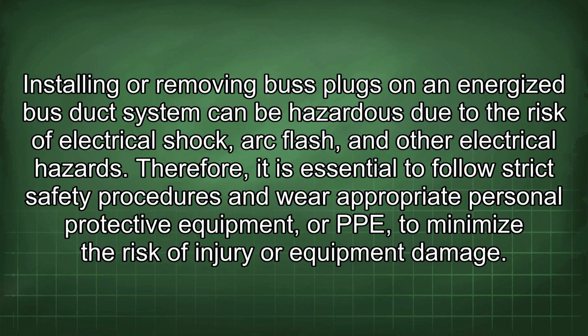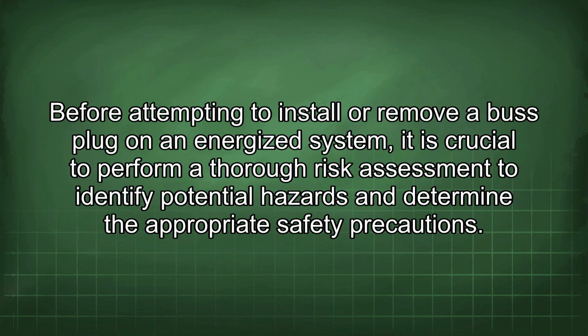Installing or removing bus plugs on an energized bus duct system can be hazardous due to the risk of electrical shock, arc flash, and other electrical hazards. Therefore, it is essential to follow strict safety procedures and wear appropriate personal protective equipment, or PPE, to minimize the risk of injury or equipment damage. Before attempting to install or remove a bus plug on an energized system, it is crucial to perform a thorough risk assessment to identify potential hazards and determine the appropriate safety precautions.